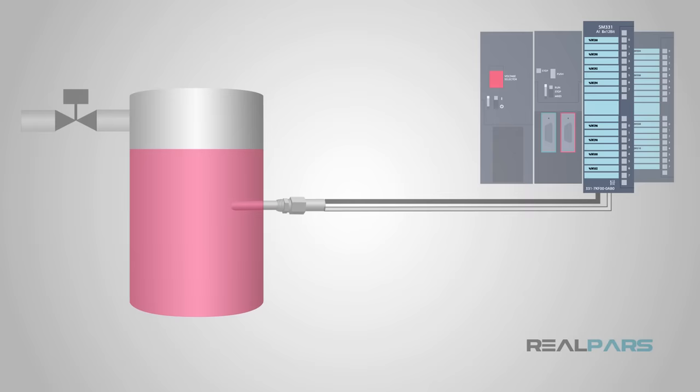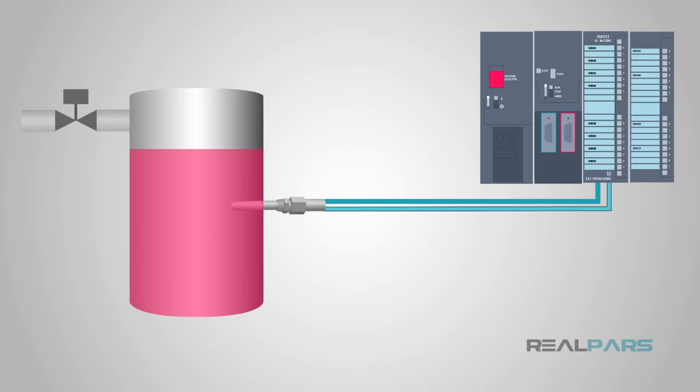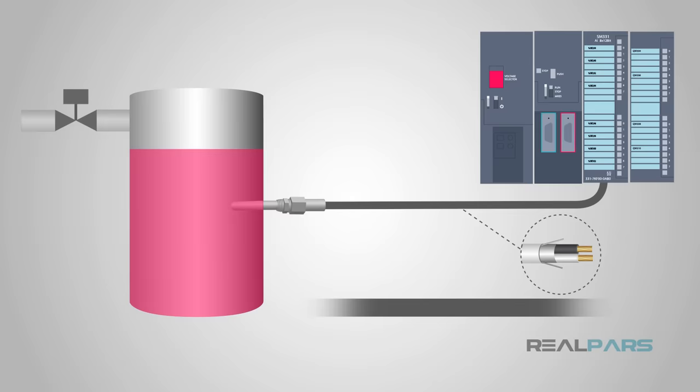The wires used to connect the thermocouple to the module must be made specifically for that type of thermocouple. The wrong kind of wire will make the signal useless. Because the signals are at such a low voltage, the wires need to be well shielded and carefully routed away from higher voltage wiring.